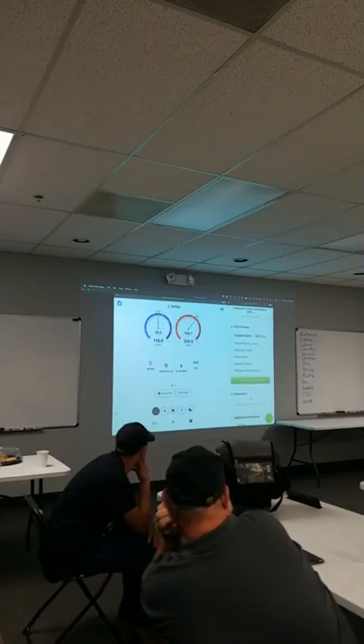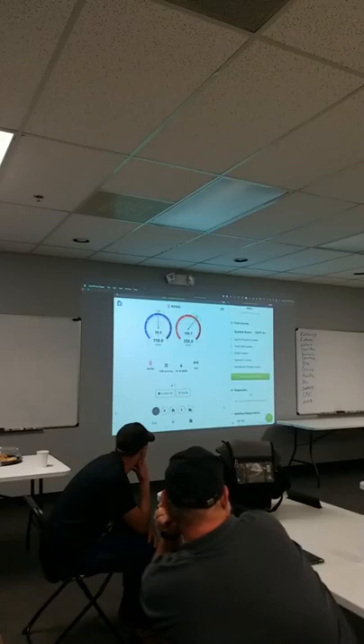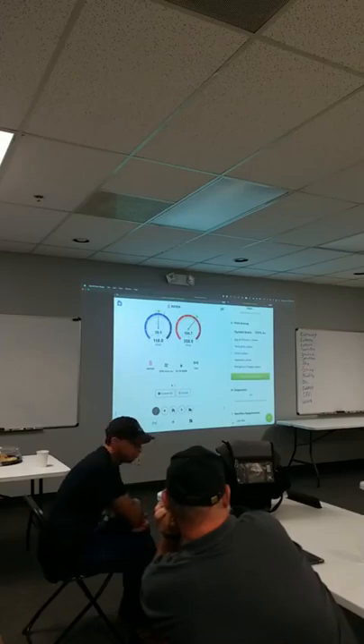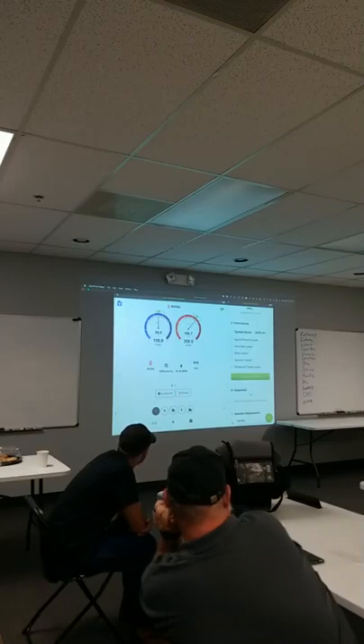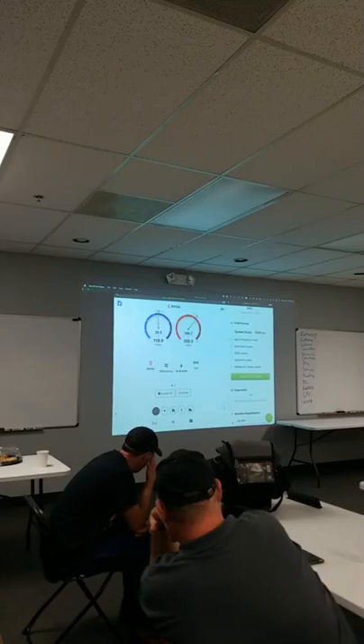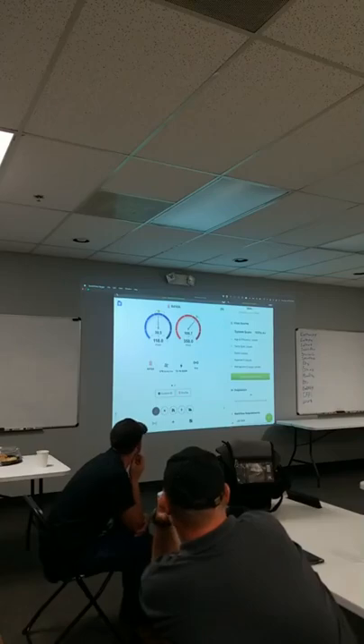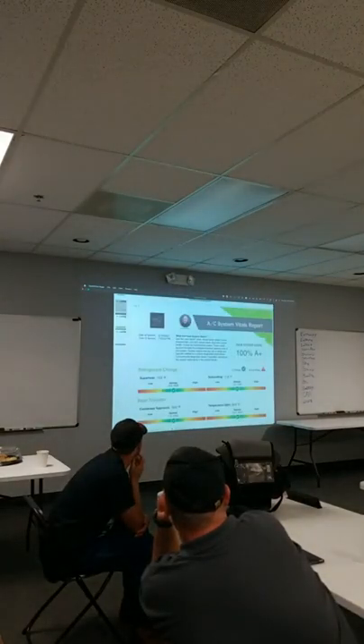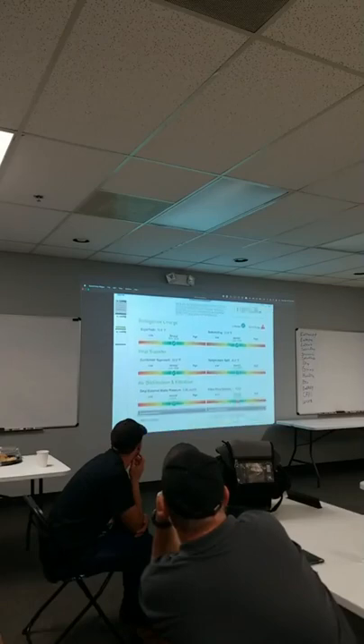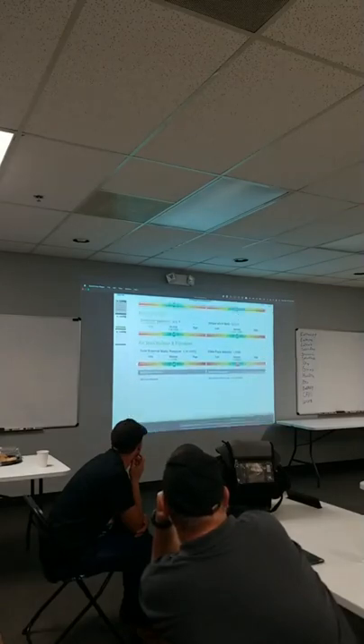The idea here is that we took a bunch of the industry studies that were based upon age and efficiency of equipment, temperature split losses, static pressure losses, approach losses, and refrigerant charge losses, and how they impact operation of the system. So now we run a score that is an A through F on that system. As soon as the system starts up, we're grading it. And then at that point, you can actually generate a vitals report, which we could share with the homeowner or the business owner, showing what's going on and if there's any issues.